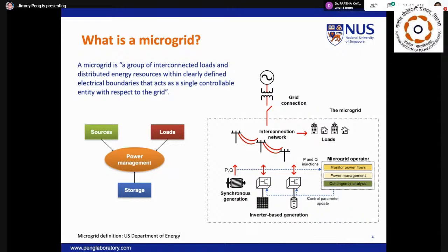In essence, we need to coordinate generation resources, electrical loads, and possible storage within the microgrid in a near real-time environment. This is a complicated problem, as a microgrid can consist of a mix of generation profiles, including synchronous generators, inverter-based generators, and electrochemical storage devices. But more importantly, the classic concepts we learned from power engineering textbooks may not be suitable, considering a microgrid has a high R/X ratio, exhibiting strong coupling between the active and reactive power components.